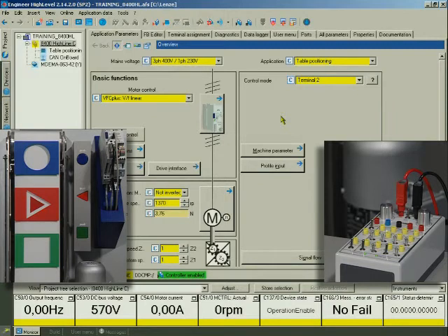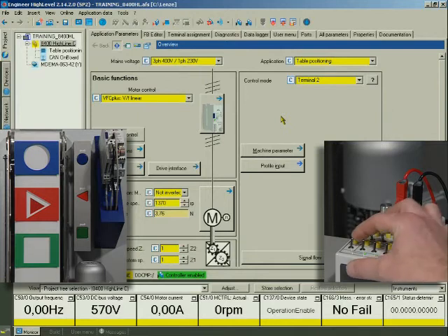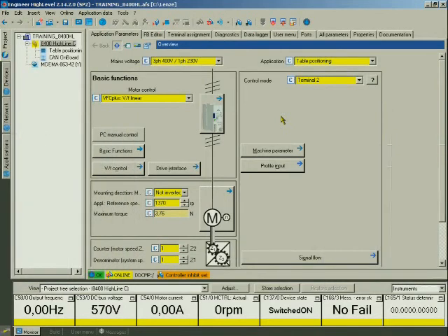Via digital input 5 and digital input 6, we select profile 3. Via digital input 7, we'll now start the positioning. The red triangle carries out a complete revolution. It is in the starting position again. We'll now complete the positioning with controller inhibit. You have commissioned the table positioning application successfully.